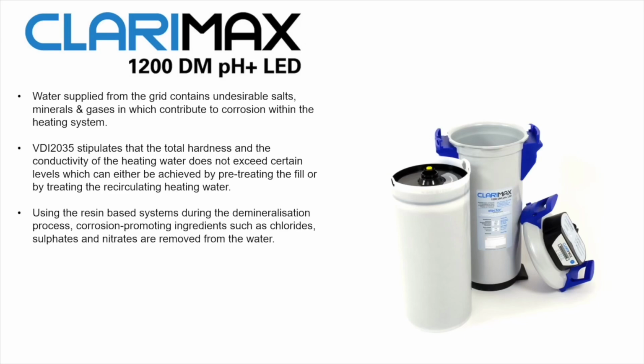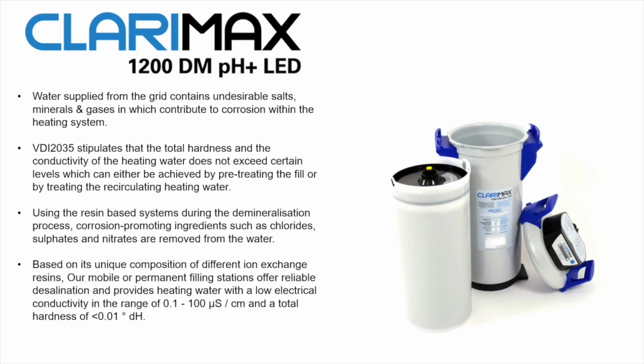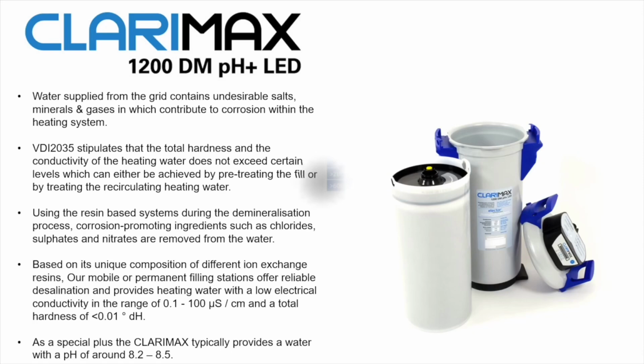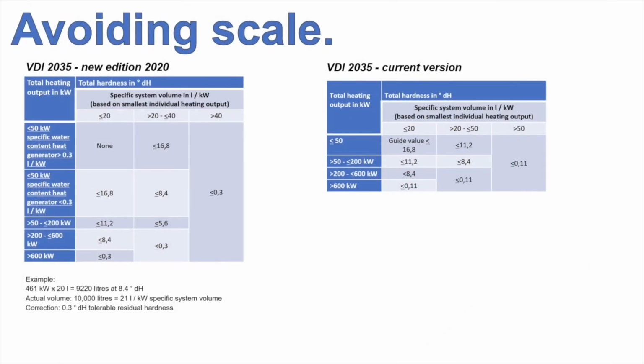Using a resin-based system, during the demineralisation process, corrosion-promoting ingredients such as chlorides, sulfates and nitrates are removed from the water. Based on a unique composition of different ion exchange resins, our mobile or permanent filling devices offer reliable desalination and provide heating water with a low electrical conductivity in the range of 0.1 to 100 microsiemens and a total hardness of less than 0.01 German degrees. A special plus when using the Clarimax is it will typically provide a pH of around 8.2 to 8.5. What we have here is a table which shows what we're looking for in terms of total hardness.